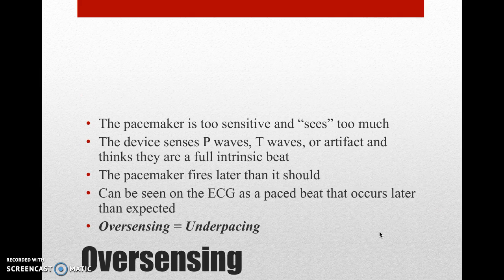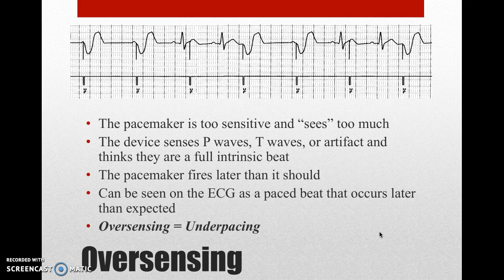In oversensing, the pacemaker is too sensitive and sees too much. The device senses P waves, T waves, or artifact and thinks they are a full intrinsic beat. The pacemaker fires later than it should. This can be seen on the ECG as a paced beat that occurs later than expected. Oversensing causes underpacing.